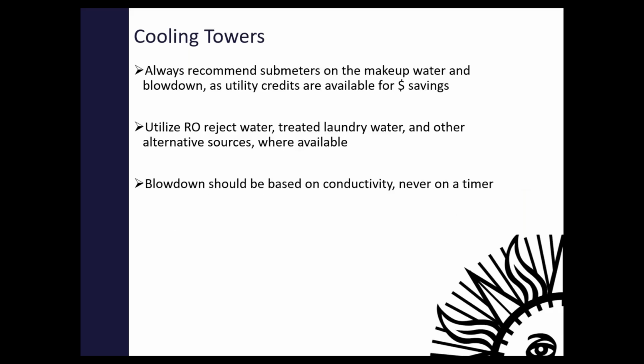But what else can we do to increase our cycles of concentration? You can also utilize different sources of water. If we use a source of water that we were going to pipe down the drain anyway, like AHU condensate, if we were to recover that, our RO reject water, any sort of alternative water source that's relatively clean, not gray water necessarily. I don't think you can use hand washing water, but these other sources of water should be able to be used as long as you pre-treat it. Make sure you're not pumping in water that's very salty or something like that, or has a high mineral content. You just have to check that you treat the water correctly. And then, of course, blowdown should be based on conductivity.